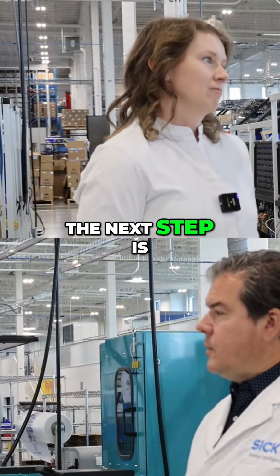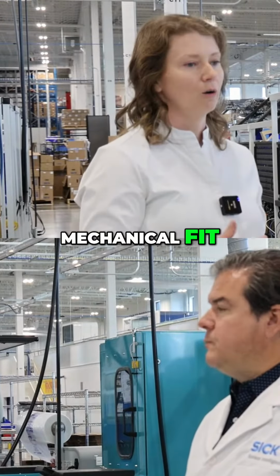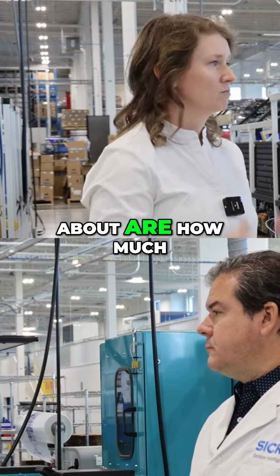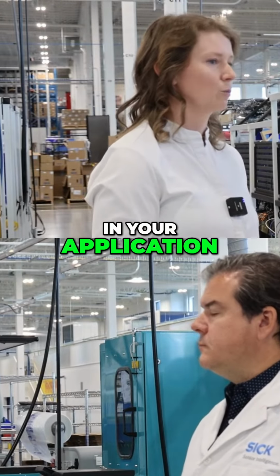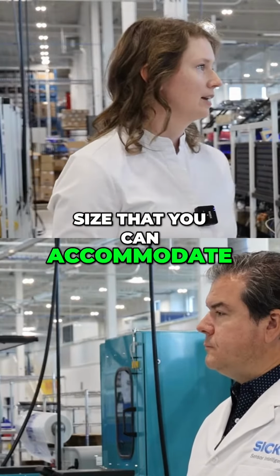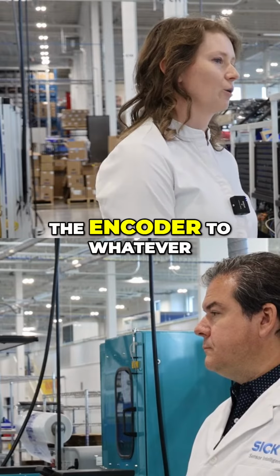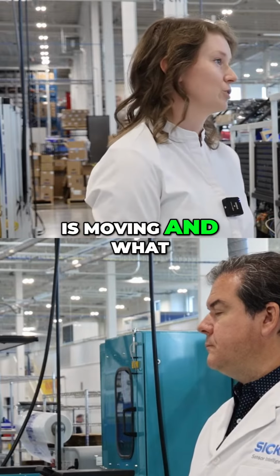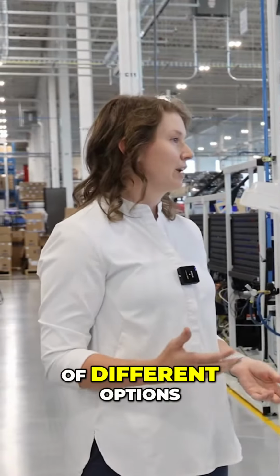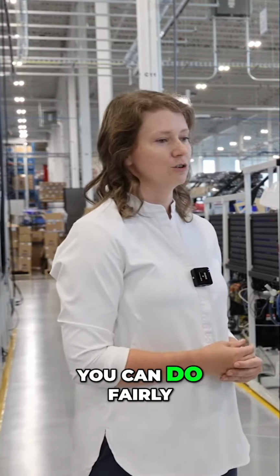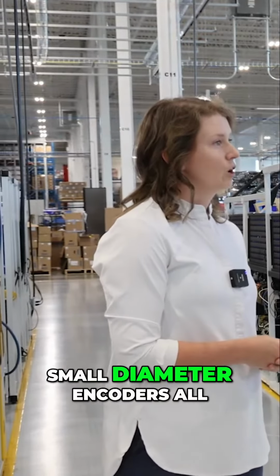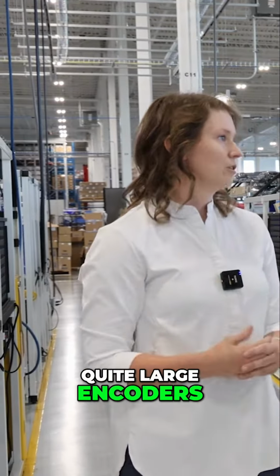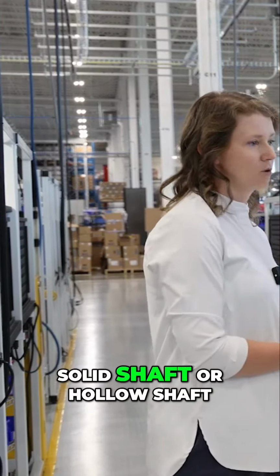The next step is mechanical fit. And so the things that you want to think about are how much space do you have in your application? What is the physical size that you can accommodate? And then how are you going to couple the encoder to whatever is moving and what you want to sense? So there's a lot of different options. There's a lot of variety. You can do fairly small diameter encoders all the way up to quite large encoders. You can also have solid shaft or hollow shaft.